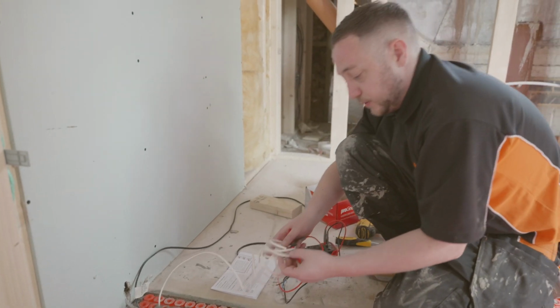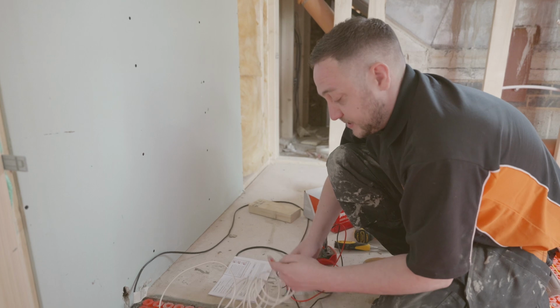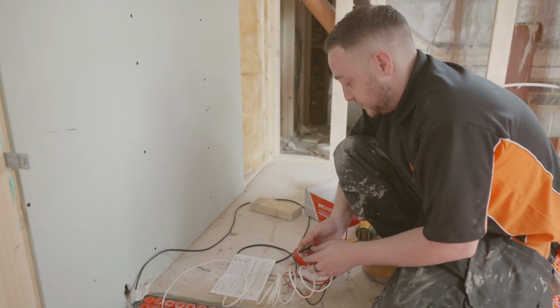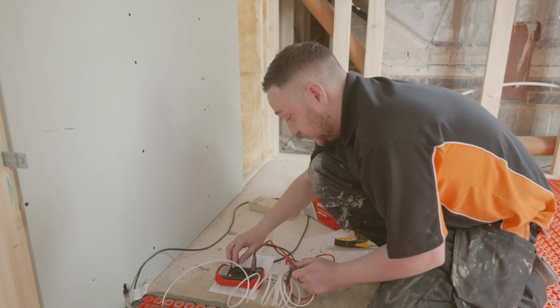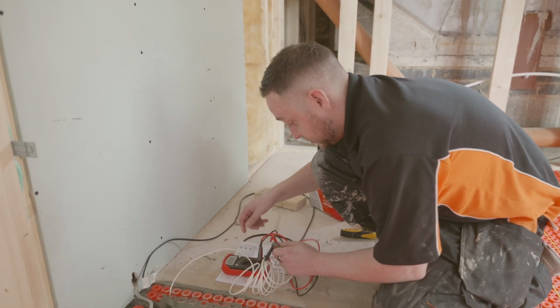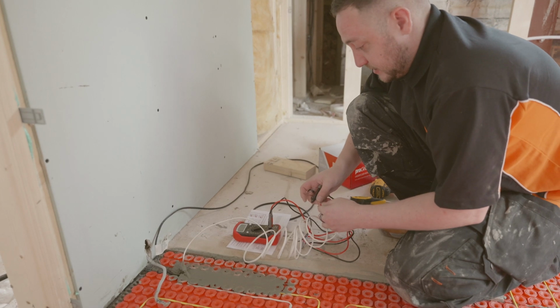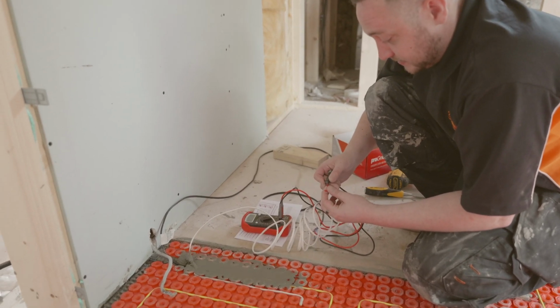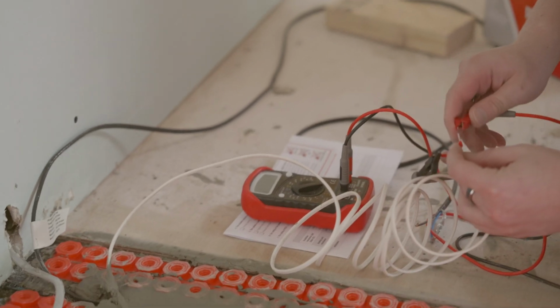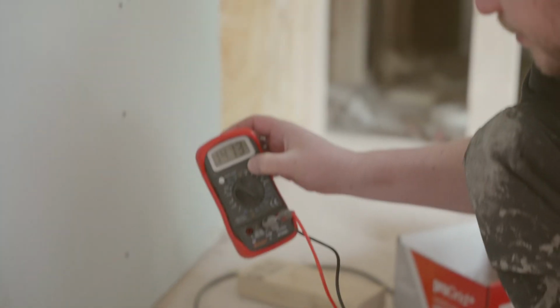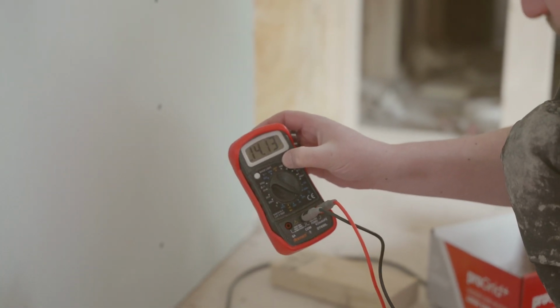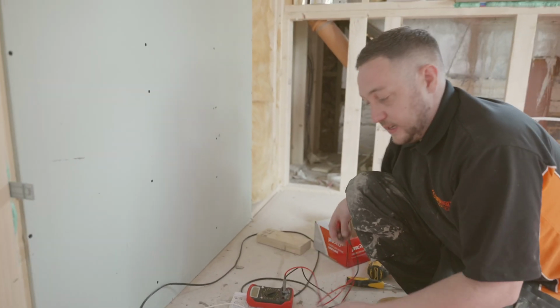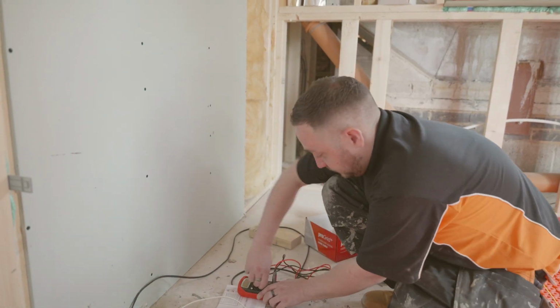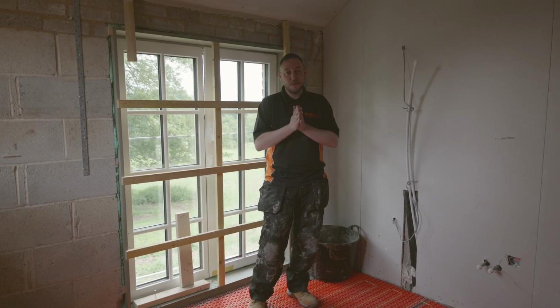Now, the resistance of your floor sensor is going to be very high. It's in the order of between 8 and 20,000 ohms. So we need to change the setting on our multimeter. Set that to 20k, and we should get somewhere between about 8 and 20,000. Yep, so there we go. We've got 14.14k. So 14.13 thousand. So we know that our floor sensor is fine as well. That completes the installation of our ProGrid system.